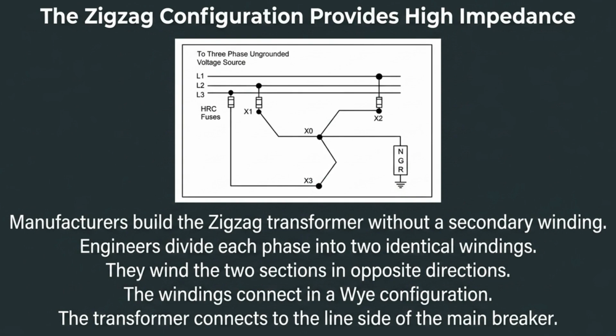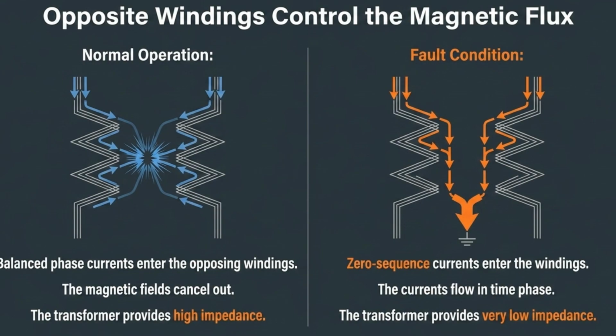It uses no secondary winding, instead dividing each phase into two sections wound in opposite directions and connected in a Y configuration to the line side. These opposing windings control magnetic flux. Under normal conditions, balanced currents cancel out, providing high impedance. However, during a fault, the currents flow in time phase, resulting in very low impedance.